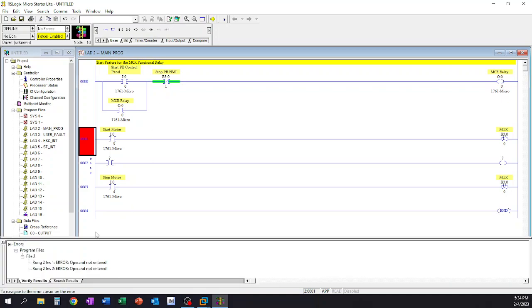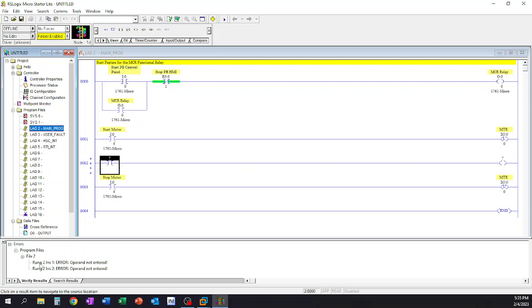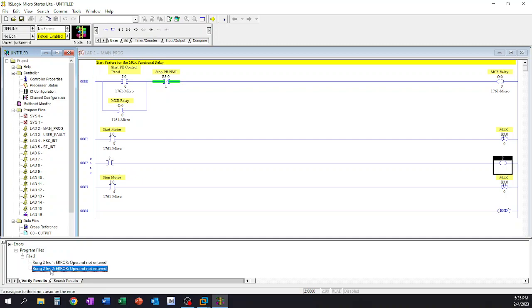If it wasn't okay, and I'll just add something here so that we can say it's not okay, what it would do is pop up this window telling us where the errors are. It's going to tell us the program files where it's located, it's going to tell us what file it's in. So we look at our project tree over here, it tells us the program files and it tells us ladder 2 or file 2 of the program files is where our issue is, and then it's also going to tell us at rung 2.